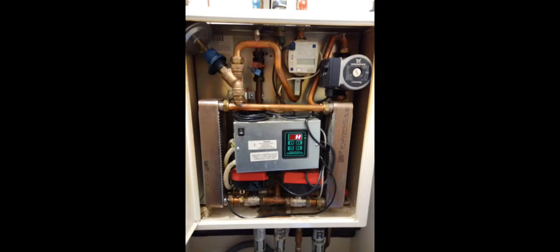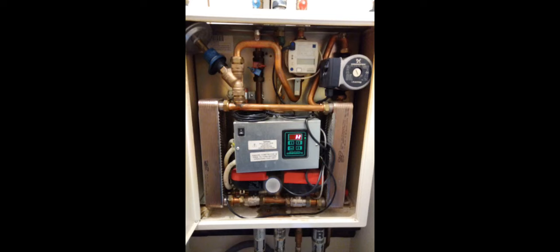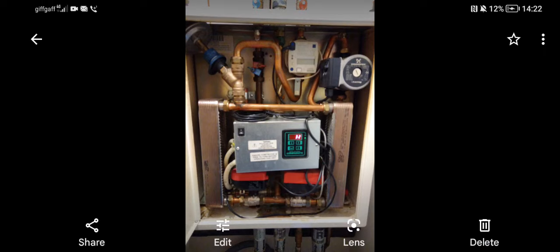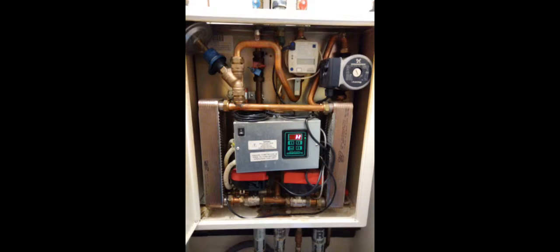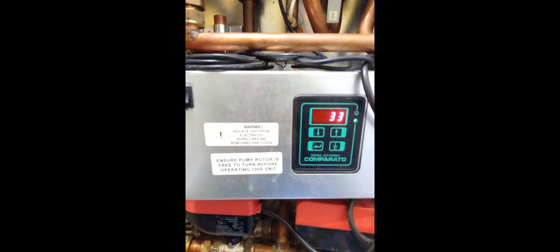Okay. Here's me working on an HIU unit. At times they were asking us to go in the flat and work on the HIU units when they weren't working. So what would I do? I would tend to see if the pump was running. I would also make sure obviously that the heat was coming in. I would check actuators to make sure that they are opening. Sometimes you have to even remove them, see if the pin's stuck and things like that. I'd be looking for any circulation issues.